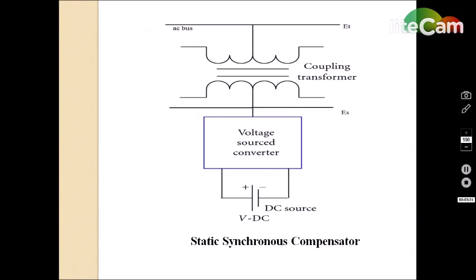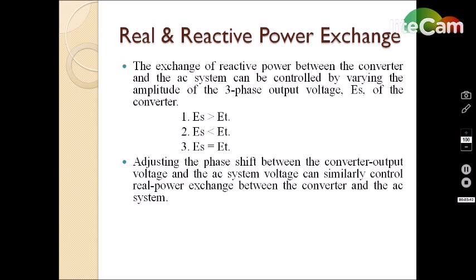What will happen when ES is equal to ET? There will be no reactive power exchange, so the STATCOM is said to be in a floating state. This is how reactive power is exchanged in STATCOM. Real power can also be exchanged by adjusting the phase shift between the output of the three-phase voltage source converter and the bus voltage.